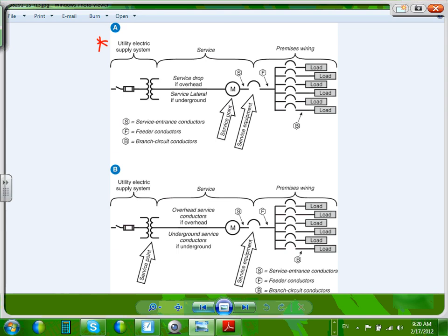If I put my service point in this area, see where my service point is right now, I'm going to emphasize, my service point is right here or right here, okay? Then this area is still operated and owned by the utilities, called service drop overhead or service lateral underground. And this is the one that I own and operate in this case. If I put my service point right here, this area here is my jurisdiction, the premises. This area is my jurisdiction. Most likely it includes the overcurrent protection device too. So most likely, they bring the feeder. If the service point is at the meter, then it also includes the feeder from the meter right here.